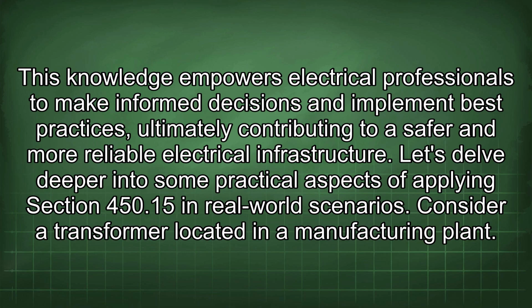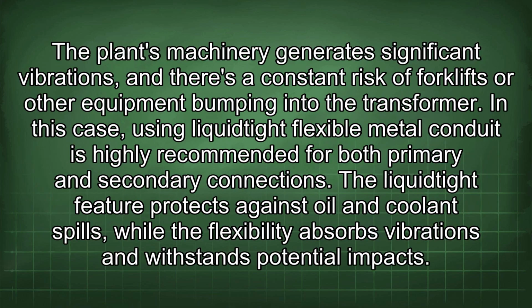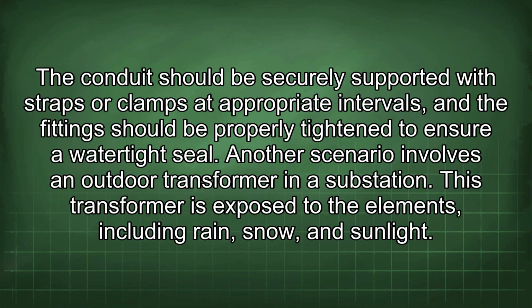Consider a transformer located in a manufacturing plant. The plant's machinery generates significant vibrations, and there's a constant risk of forklifts or other equipment bumping into the transformer. In this case, using liquidtight flexible metal conduit is highly recommended for both primary and secondary connections. The liquidtight feature protects against oil and coolant spills, while the flexibility absorbs vibrations and withstands potential impacts. The conduit should be securely supported with straps or clamps at appropriate intervals, and the fittings should be properly tightened to ensure a watertight seal.